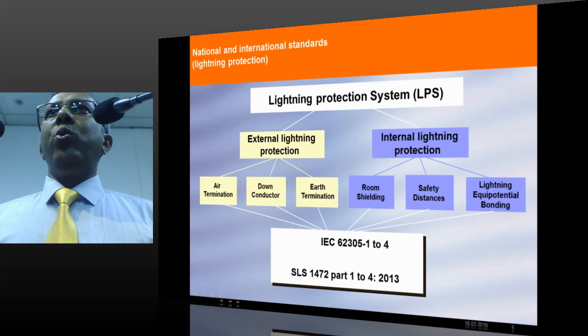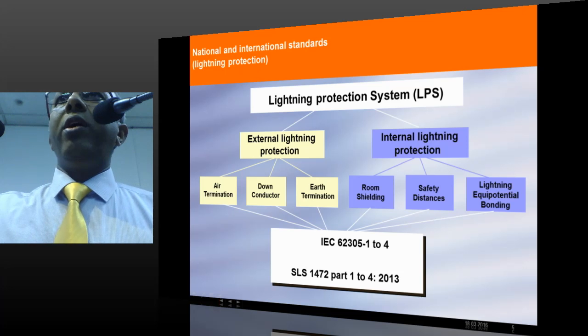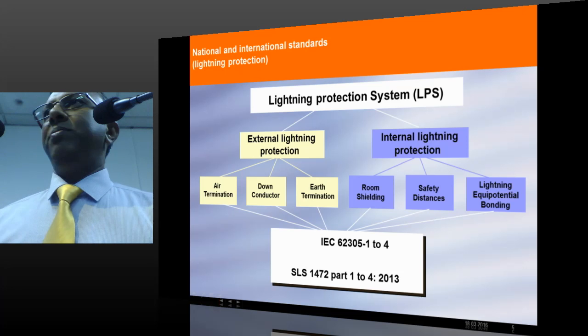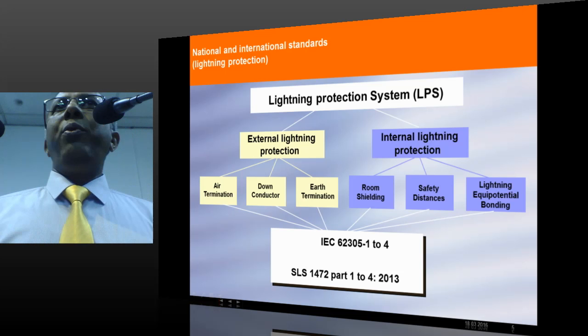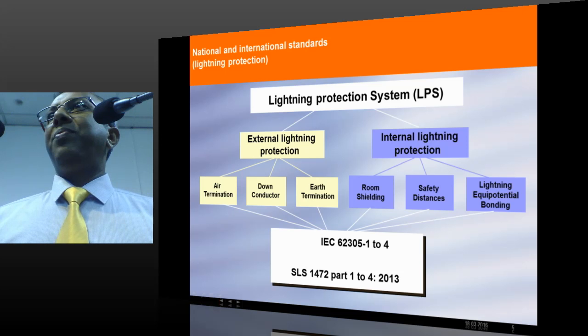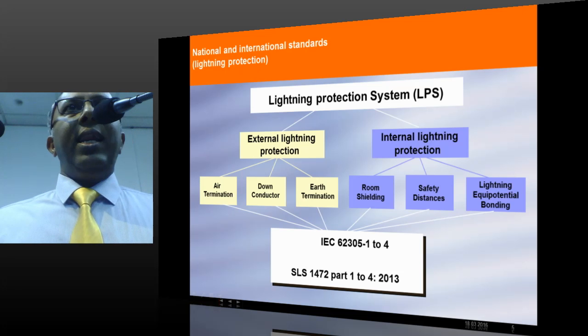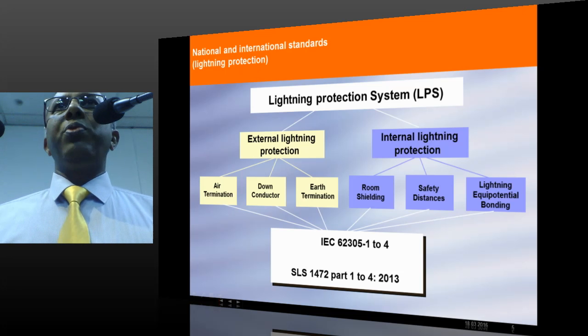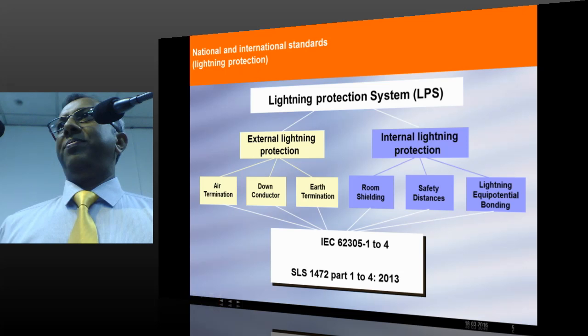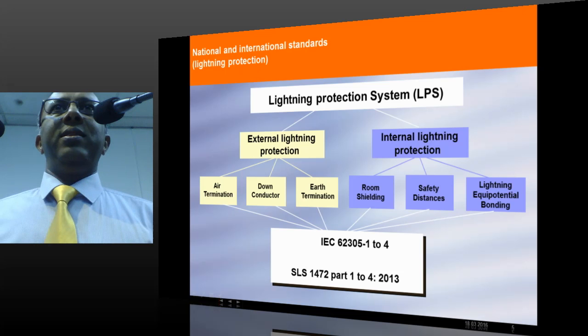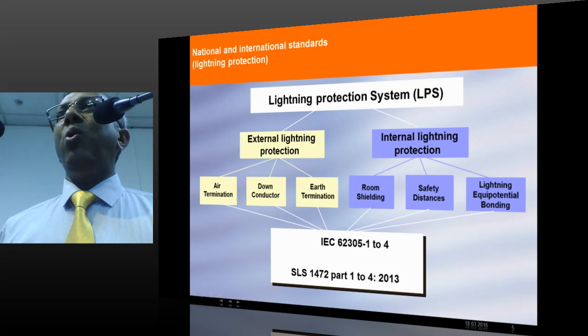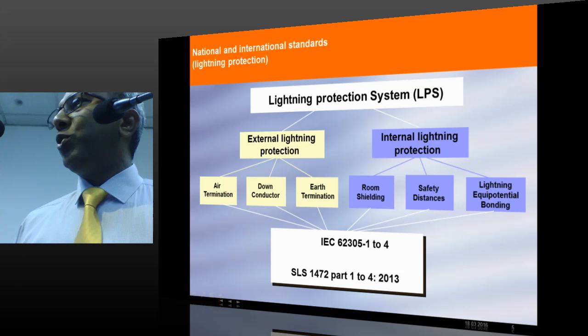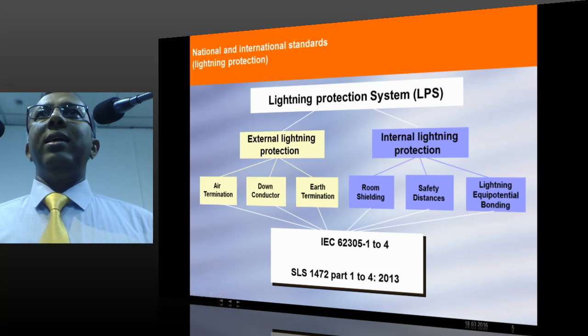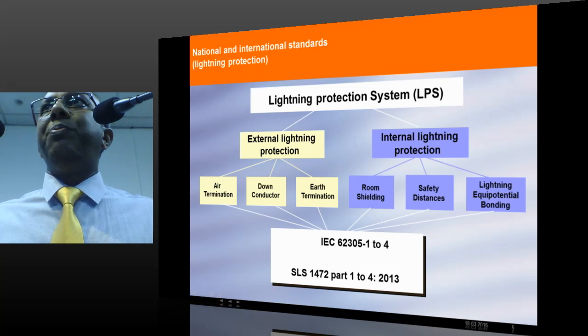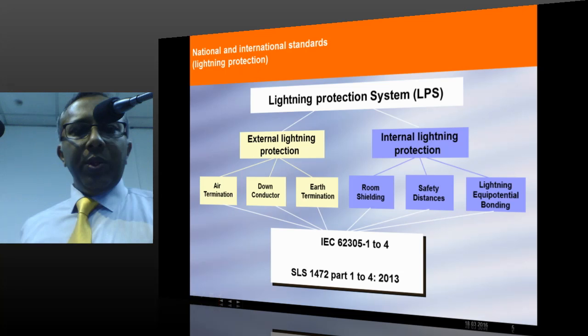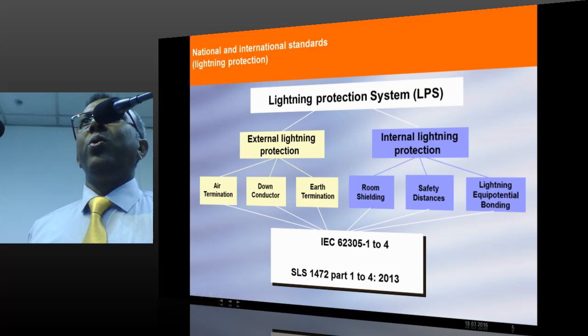Earthing, what we generally do is each down conductor is connected to a vertical or a horizontal earth electrode. Is it the right way? Yes, it can be. But nowadays there is no building without electricity. Every building has electricity and electrically operated equipment. And in a building with an electricity connection, the most preferred earthing system is to have a ring conductor. A ring conductor means a conductor all around the building. Or the second way is to use foundation earthing. Foundation earthing means the steel reinforcement in the foundation can be used as your earth pit, or as the earthing system which will dissipate your lightning current. So these 3 points are important with respect to the external lightning protection system.